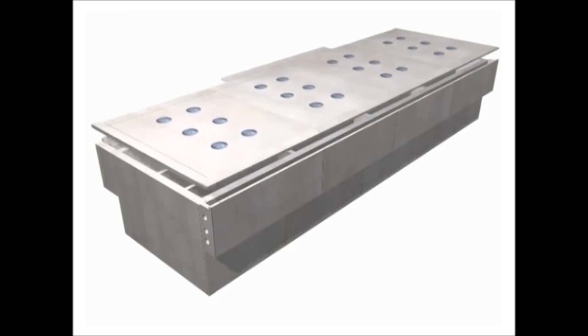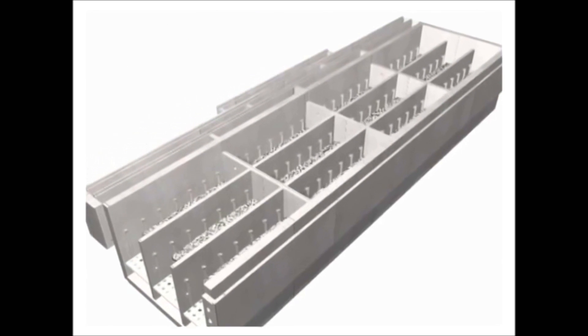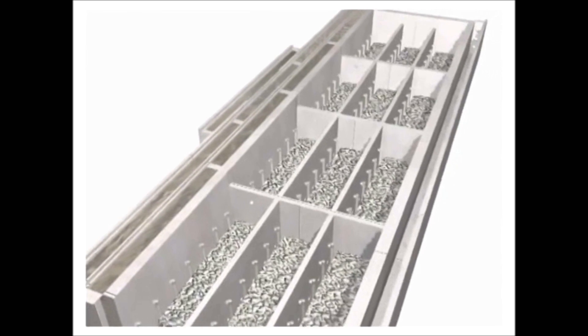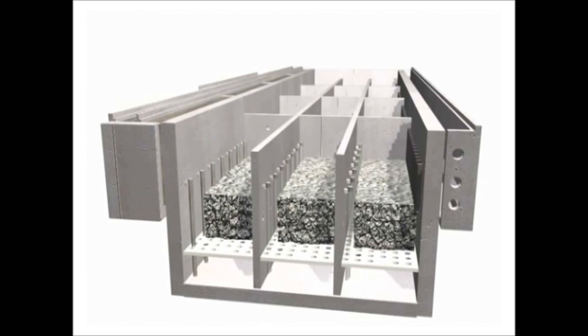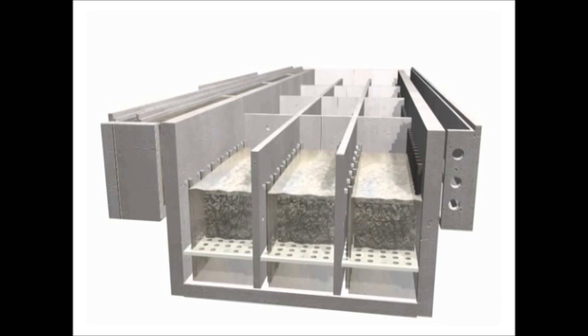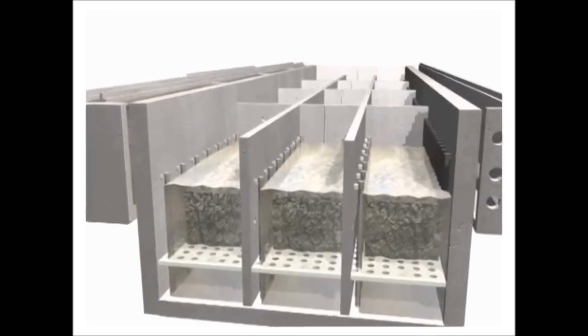Next comes the anaerobic filter. Wastewater is distributed through a series of distribution channels which regulate equal distribution of wastewater flow. Inside the chamber, pipes direct the water stream from top to bottom several times in a row. The chambers are constructed in series to digest remaining degradable substances with the help of a filter material, which provides a breeding or carrier place for bacteria, allowing a larger contact surface for wastewater during passage. At the end of this treatment, about 90% of the original pollution load is removed.